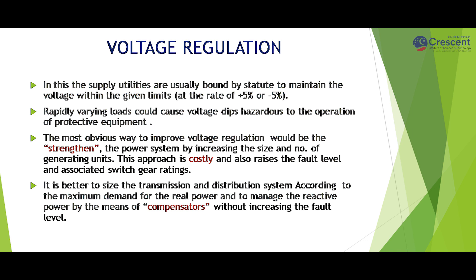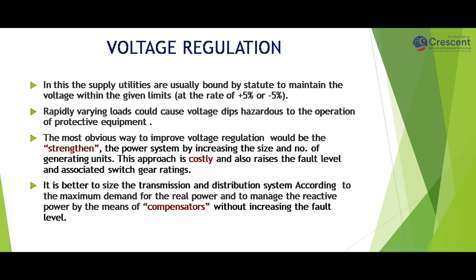Another objective of load compensation is voltage regulation. Supply utilities are usually bound by statute to maintain voltage within given limits, typically plus or minus five percent. Rapidly varying loads could cause voltage dips hazardous to the operation of protective equipment. For example, an electric arc furnace used to melt metal causes large voltage variations, and carbon arc bulbs cause discomfort to the eyes, so constant voltage must be maintained.